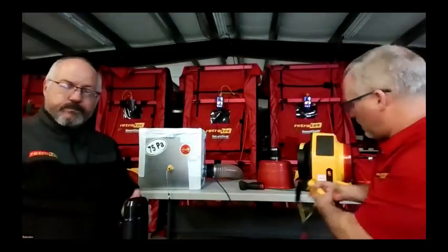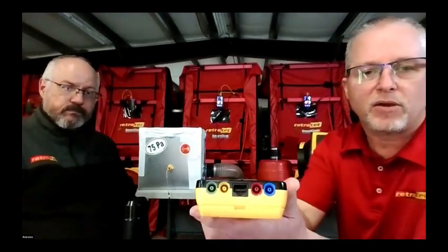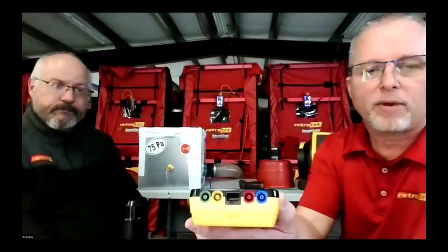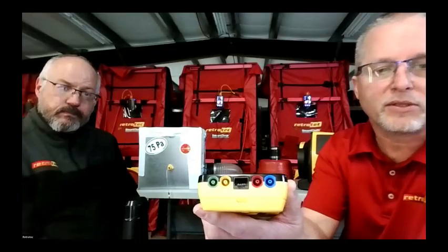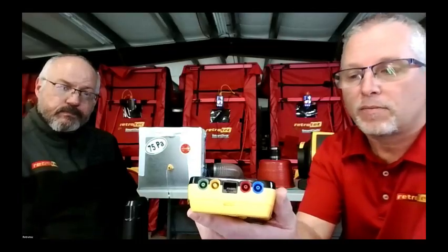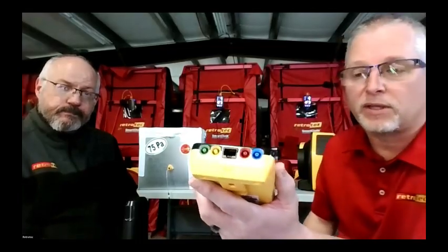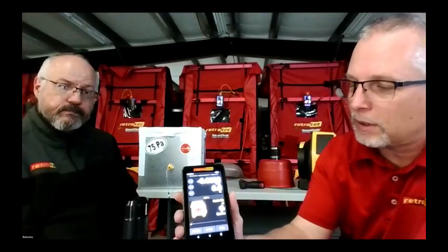The DM32X is our workhorse manometer. It is a 2-channel manometer. It's got 2 ports, 2 sets, the green and the yellow, the red and the blue. The red and the blue will be used to measure your static pressure. The green and the yellow are used to measure the pressure across the fan. By measuring across the fan pressure, the DM32 will calculate out what the flow is based on the fan configuration. It's built on an Android platform.